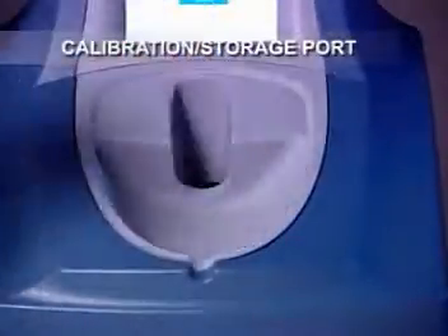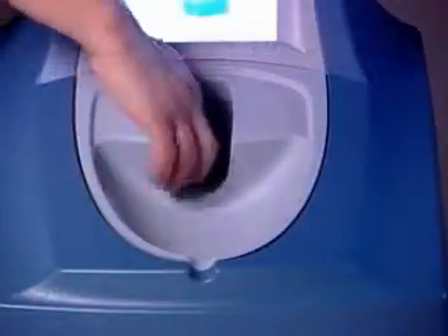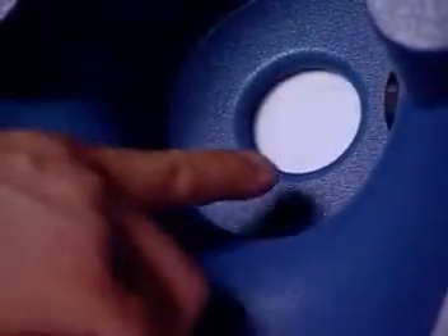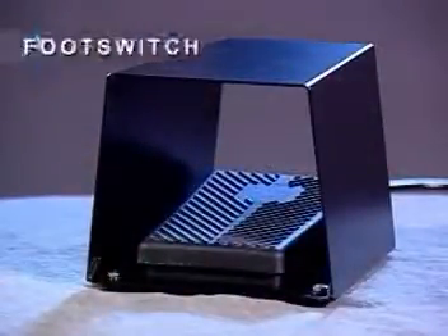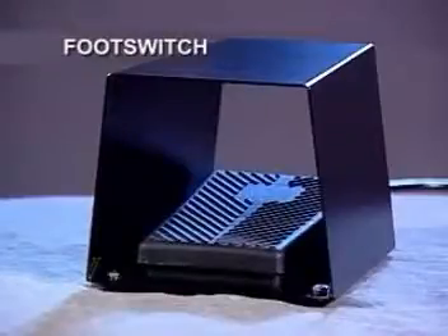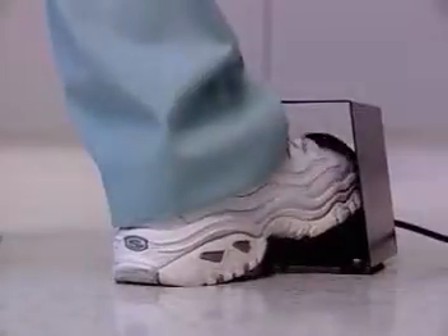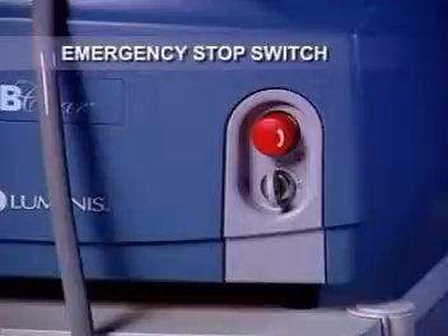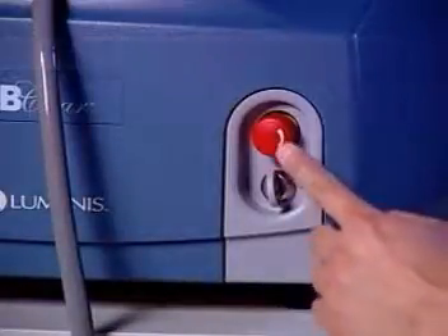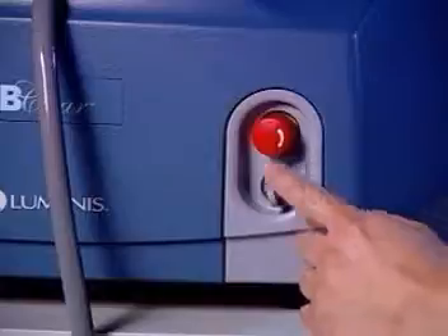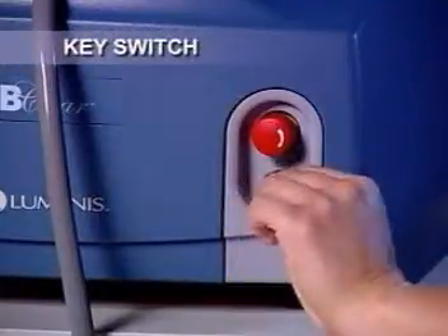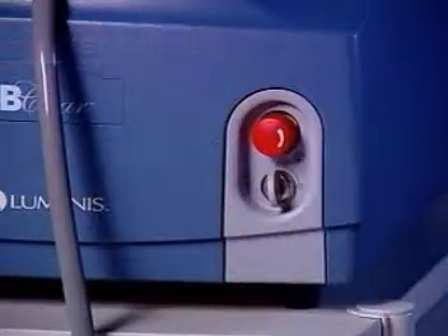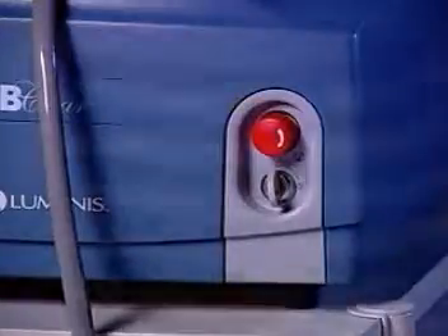Calibration storage port. To calibrate the unit, the phototherapy system is fired at an energy meter located directly below the handpiece storage port. Foot switch. Use the foot switch to activate the emission of UV light. For safety, the foot switch is entirely pneumatic, operating with air pressure rather than electricity. Emergency stop switch. The system can be shut down immediately by pushing the emergency stop button. Key switch. When the main power is on, the key switch is used to activate and deactivate the system.